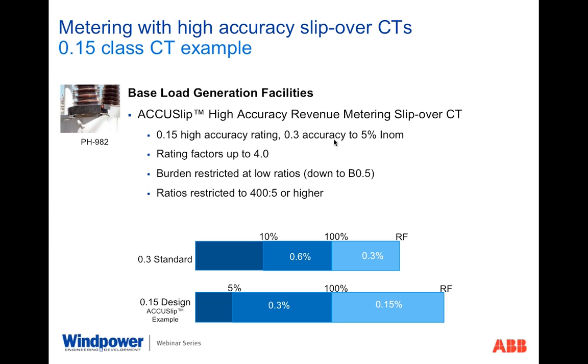And so therefore, by taking the 0.15 class, defining it in a product that's easily applied, like you see in the slip-over CT down around the 138 kV bushing in that little photograph on the upper left, we are able to get 0.15% accuracy from 100% of rated current all the way up to rating factor values. And then we could take the 0.3 revenue class that had up until then been excellent for revenue metering, take that 0.3 class all the way down to 5%, which was an advancement for the industry at the time.